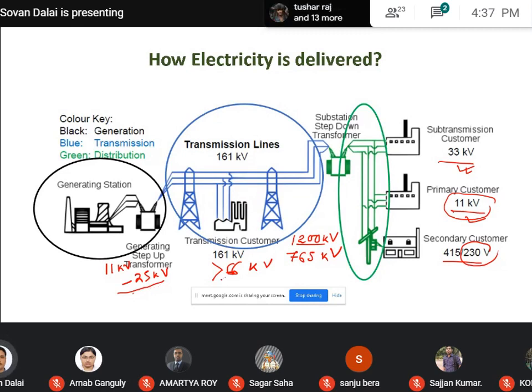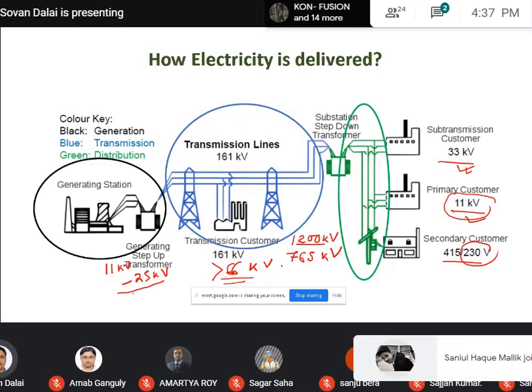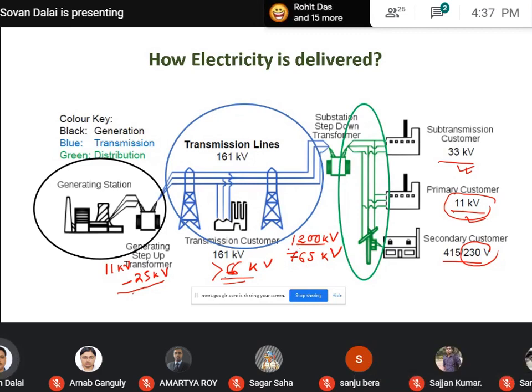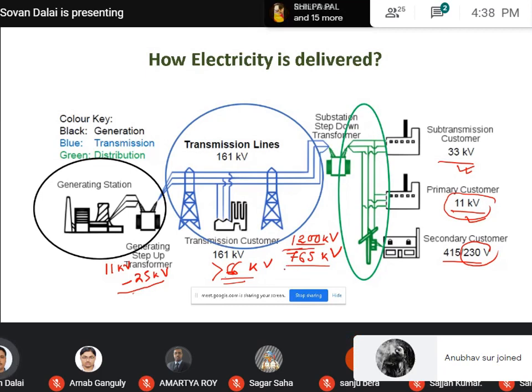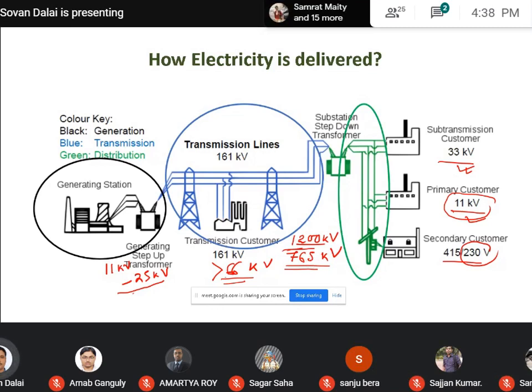And why is the transmission voltage level high? If we transmit power at high voltage, then the transmission loss is less. That is why the transmission line voltage is generally higher than the generating voltage, more than 66 kV, and it can go up to 1000 kV or more. 1000 kV transmission lines exist in our neighboring country China, and India is now commissioning 1200 kV, but in India the 765 kV transmission line is successfully running commercially.